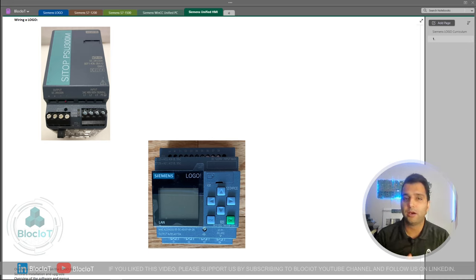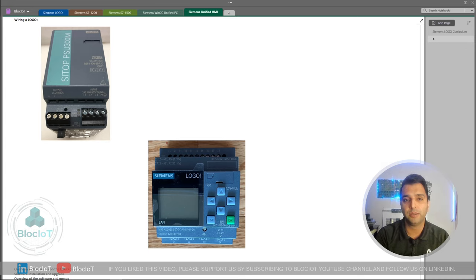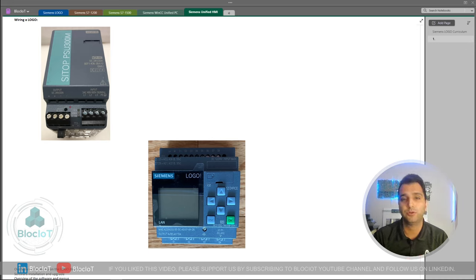The higher the amp number, the more devices the power supply can supply power to. If you are just powering up a single Logo, it really doesn't consume much — less than an amp, or 500 milliamps — and you can get the exact number from the datasheet. But we normally use a bigger power supply, minimum 2 or 5 amps. With a 20-amp power supply, you can use the same one to power sensors, actuators, and other PLC modules or HMIs in your control cabinet.